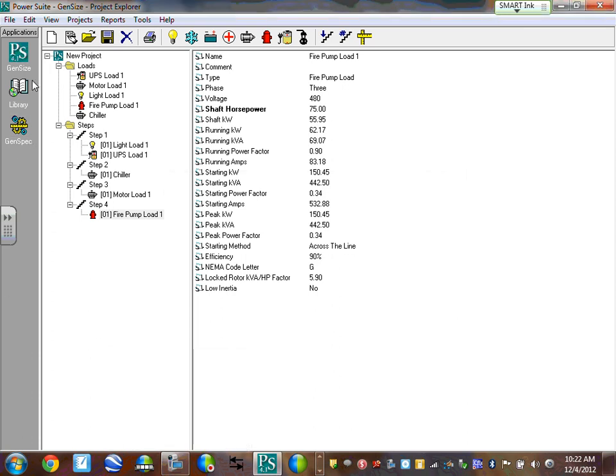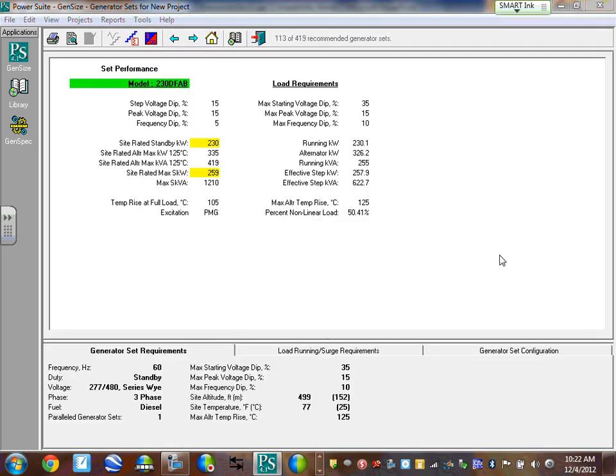Now, how do we get it to, oh, that's this one? Size it? Okay. Based on the loads that we plugged in, it picked a 230 DFAB, and you'll notice here that the voltage dip is 15%. It's limited that to the fire pump, and it's also picking a larger alternator. It's 105 degree, and it's got a PMG for an exciter, which are additional motor starting load application enhancements. It's got a bigger generator and it's PMG.